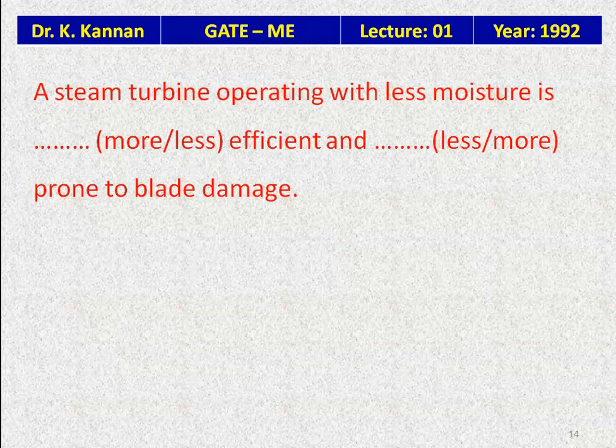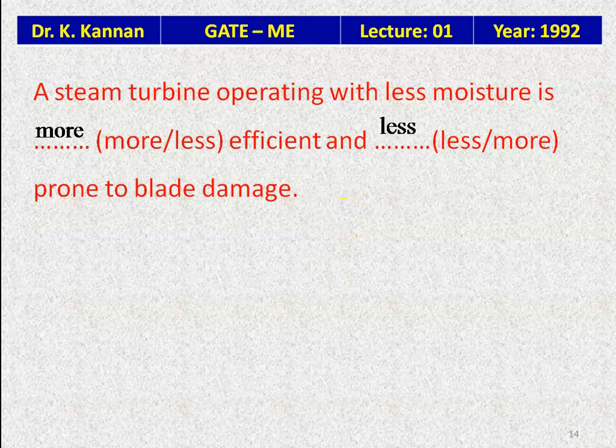Question 12: A steam turbine operating with less moisture is — more or less efficient — more or less prone to blade damage. Wet steam has moisture content. When there is less moisture, efficiency is higher. Also, the presence of moisture damages the blades; so with less moisture, there is less blade damage. The answer: a steam turbine operating with less moisture is more efficient and less prone to blade damage.